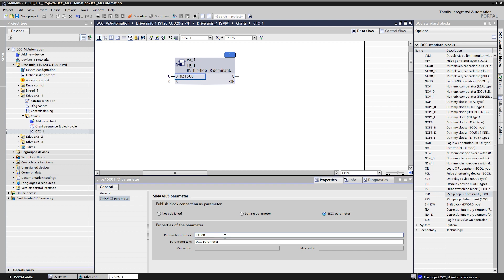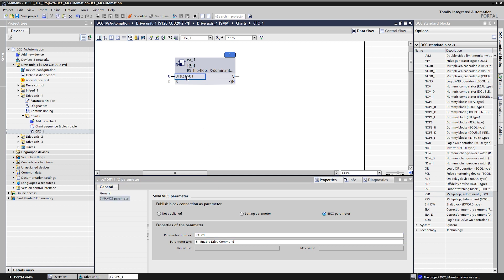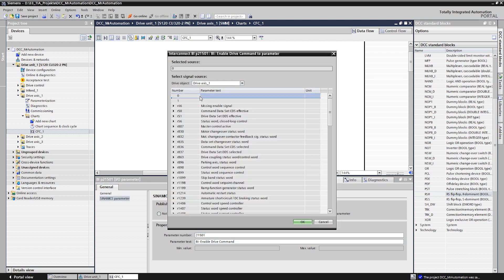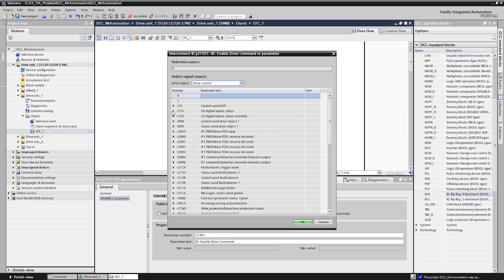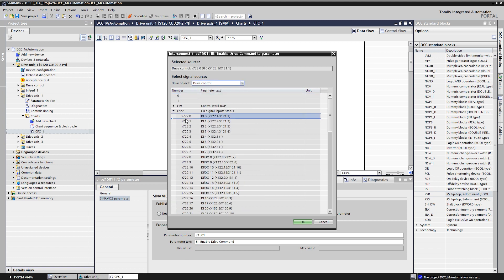In addition, we can adjust the parameter number and the parameter text here individually. All parameters published in the chart are automatically transferred to the parameter list of the axis and can also be changed from there afterwards. Now that the input is published as BICO parameter, we can connect the signal source of the digital input here. The digital inputs are mapped on the control unit in parameter R722.